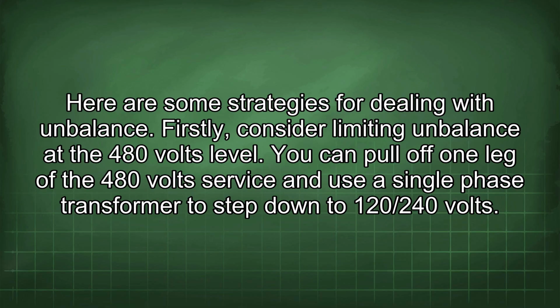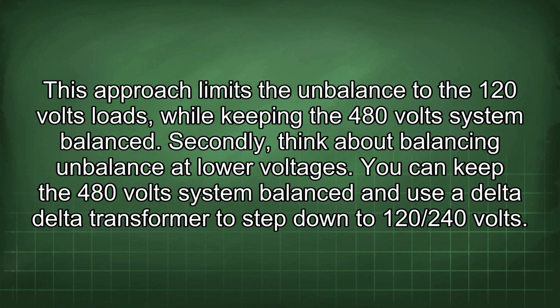Firstly, consider limiting imbalance at the 480 volt level. You can pull off one leg of the 480 volt service and use a single-phase transformer to step down to 120/240 volts. This approach limits the imbalance to the 120 volt loads while keeping the 480 volt system balanced.